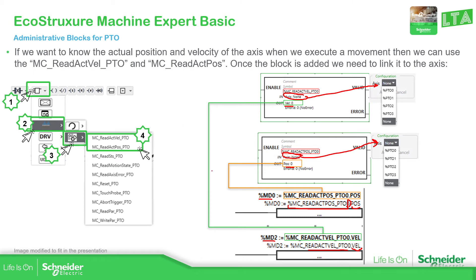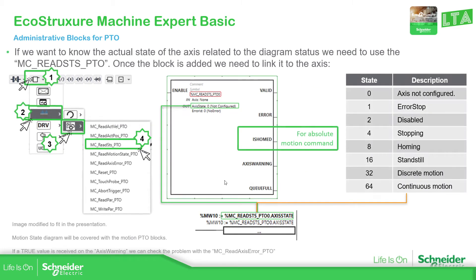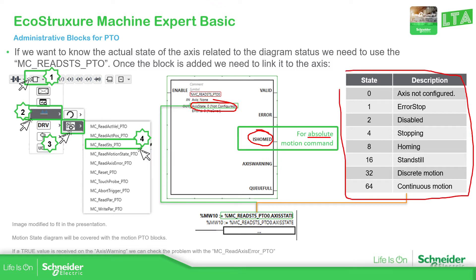If we continue, we have the read status of the PTO. This one is important because, for example, if the axis is not referenced to zero — the home — then we cannot execute the absolute movement. Something important here is the axis state, which is linked to the status of the diagram and state motion. We're going to cover that later when we start with the motion movements. This information is useful to show, for example, in the HMI.